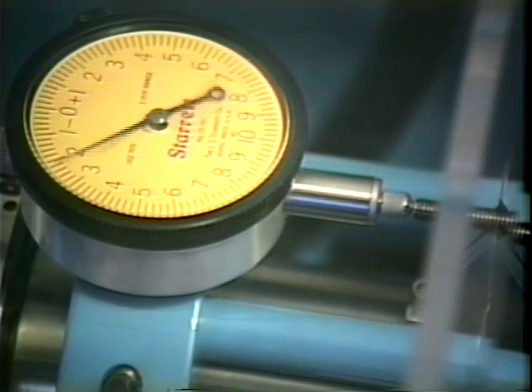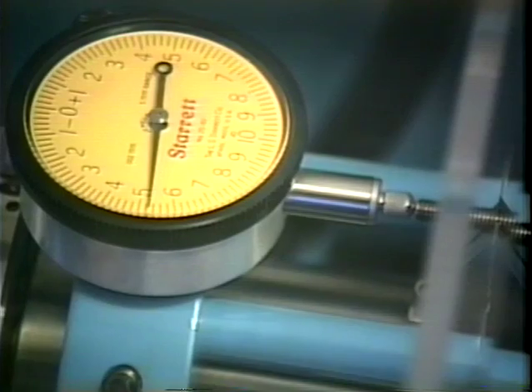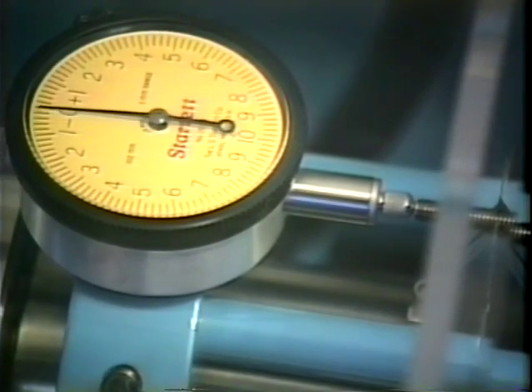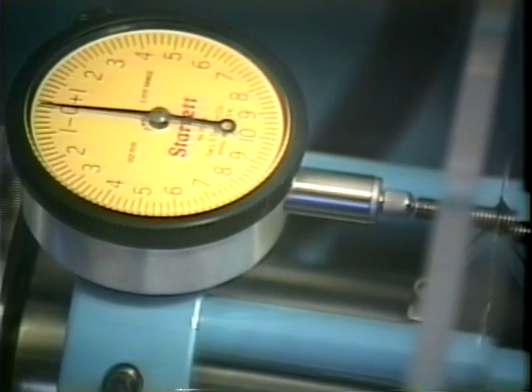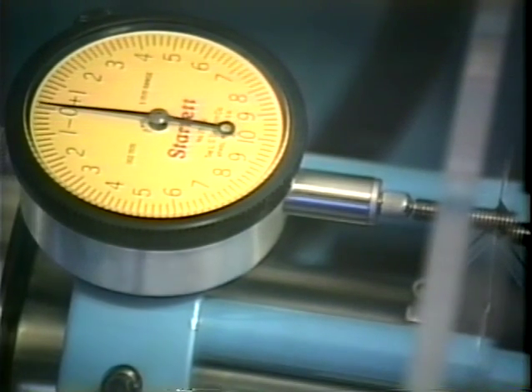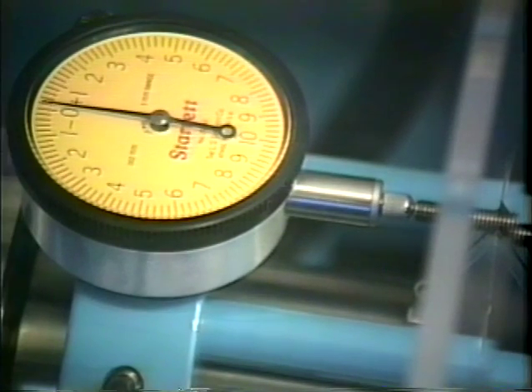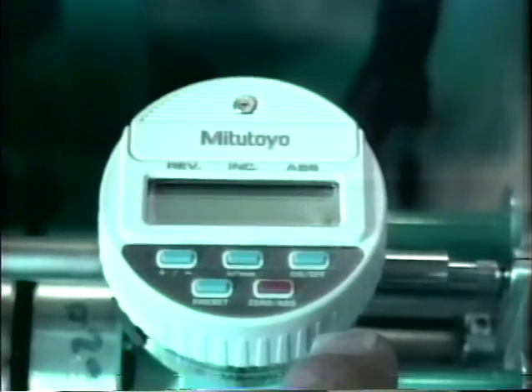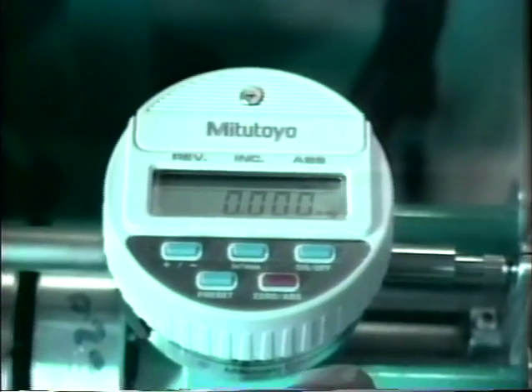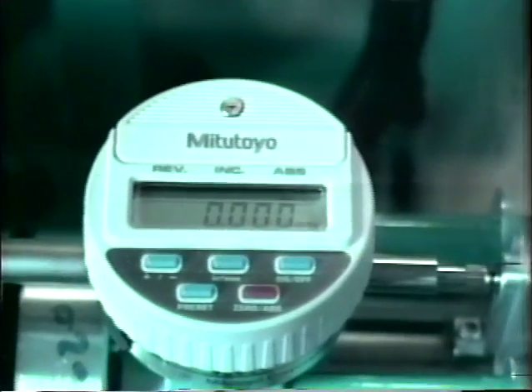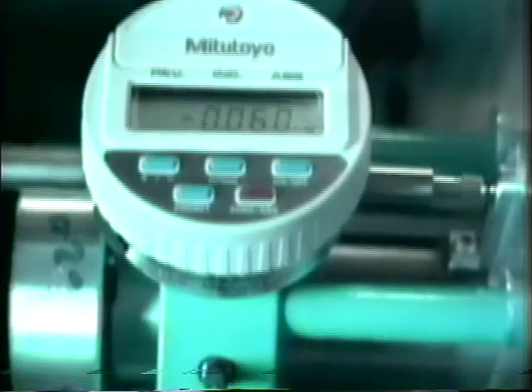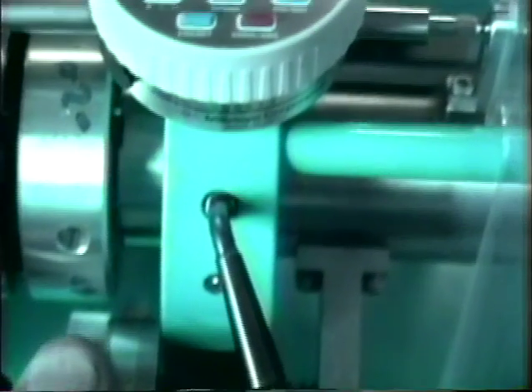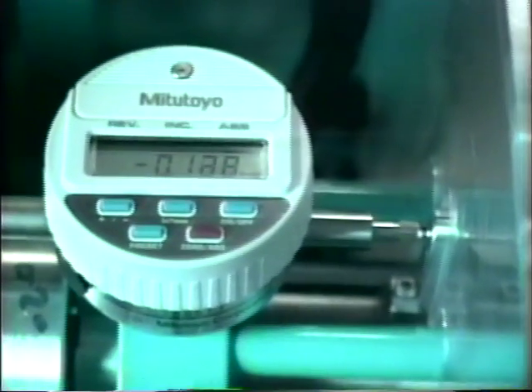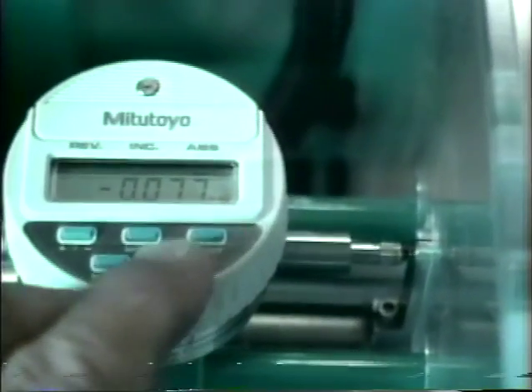To verify the calibration, we back the diamond plate away and then come in again to 0, one turn to 0, two turns to 0, verifying we have calibration of the dial indicator. Here we're showing the calibration of the new digital indicator. Turn it on by pressing the on button. Then we can advance the diamond plate in toward the glass until we have touch off on the glass. And we can zero the indicator just by hitting this red button.